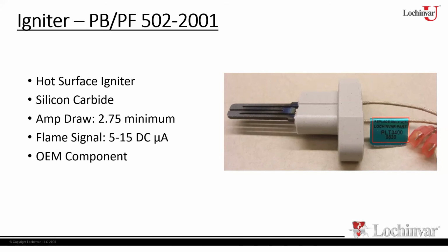Generally, it's going to operate at 8 to 12. Most often, that's where you'll see them run. You might see it go higher. That's fine. It's not a big deal. The main concern that I have with the flame signal is that it is steady. Now, am I concerned if it's weak, if I see 5 microamps at high fire? That generally tells me it's a lean gas air mixture at that point. If I see a low signal at high fire, it's typically lean.